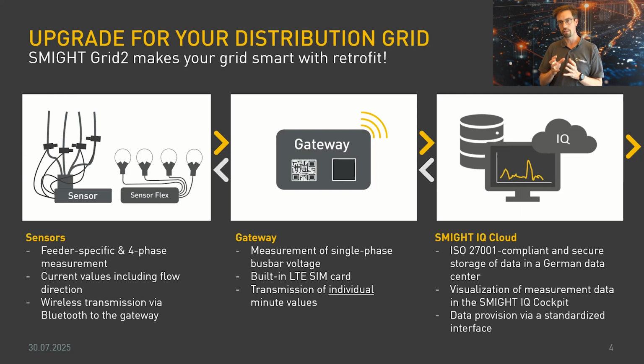That piece of data is then transmitted via Bluetooth to our gateway, which already makes it a particularly simple and clean installation because there's no cabling running between the sensors and the gateway. Then the gateway takes a single voltage measurement from the bus bar and combines those 2 pieces of data, sending them up into the cloud via the mobile networks.